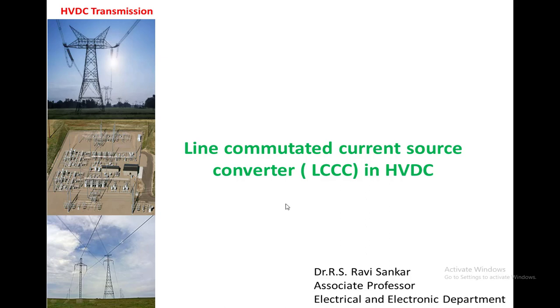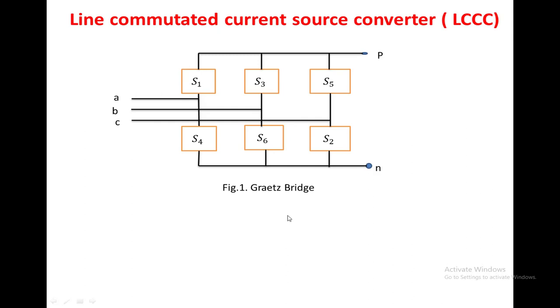In this lecture we are going to discuss about the line commutated current source converter HVDC system. This is the circuit diagram with valves S1, S3, S5, S2, S4, and S6. The numbering for the valves is given in the sequence in which we are turning on the devices. A phase, B phase, and C phase is the connected three-phase supply. By turning on and off the devices, the AC voltage will be converted to DC voltage. In the line commutated current source converter, each valve is a SCR.